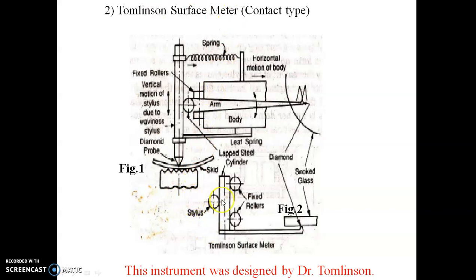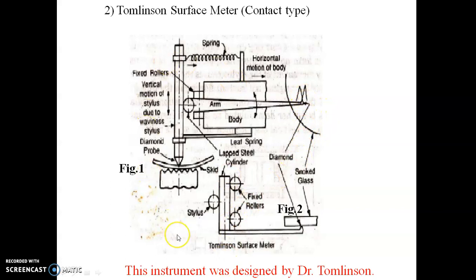In the Tomlinson surface meter, there are two rollers and the stylus and probe are connected because of spring tension. When it moves over peaks and valleys, it moves up and down. That up-and-down movement is converted into the movement of the arm, which records the exact surface roughness of an object in an enlarged scale.